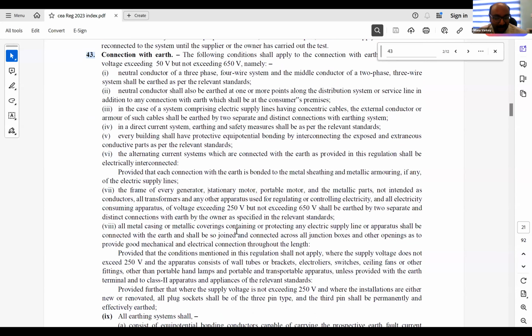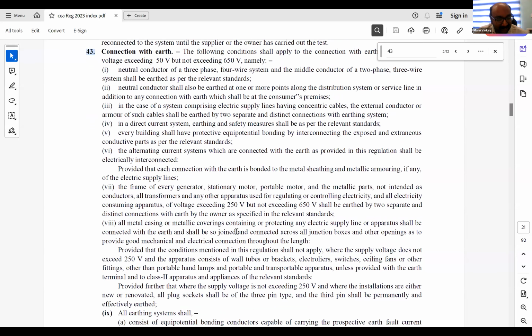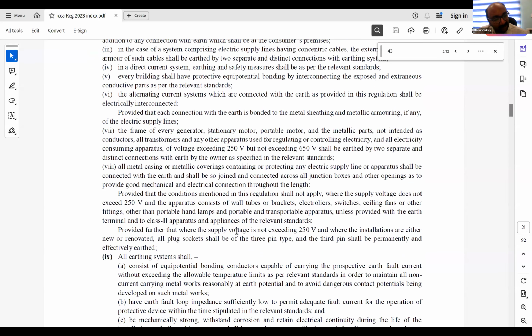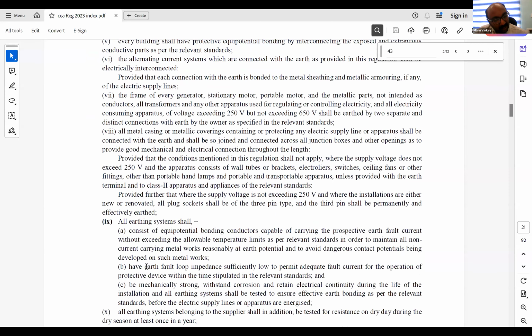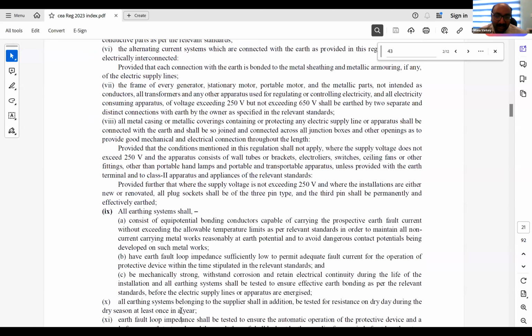If you look at regulation 43, sub-part 9, it talks about the loop impedance. All earthing systems shall have an earth fault loop impedance sufficiently low to permit adequate fault current for the operation of the protective device within the time stipulated in the relevant standards. So this means that we should design the system with a low enough earth fault loop impedance that would cause a flow of fault current sufficient for our MCB, MCCB or ACB to trip.